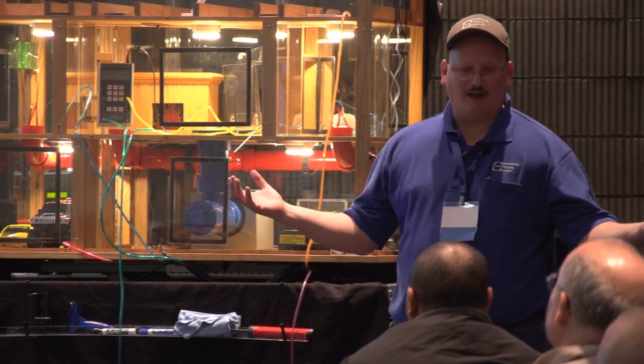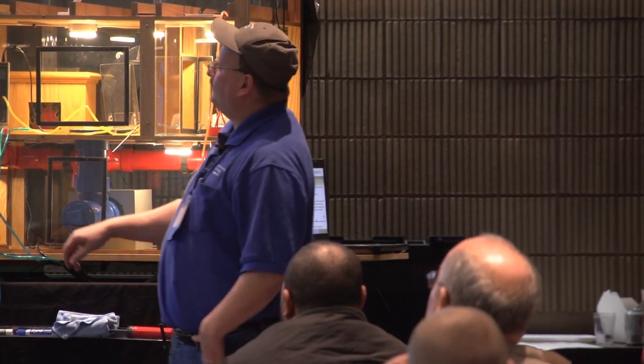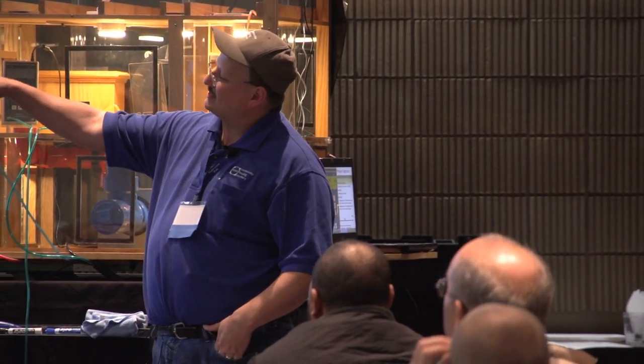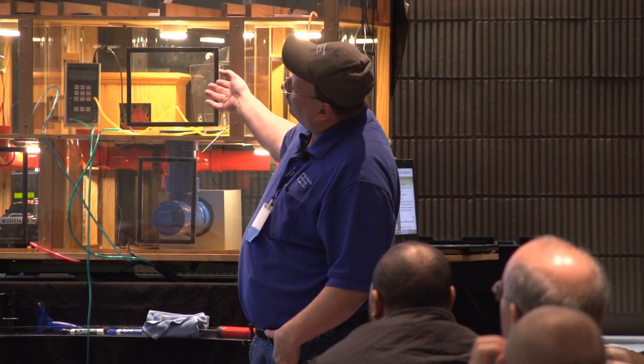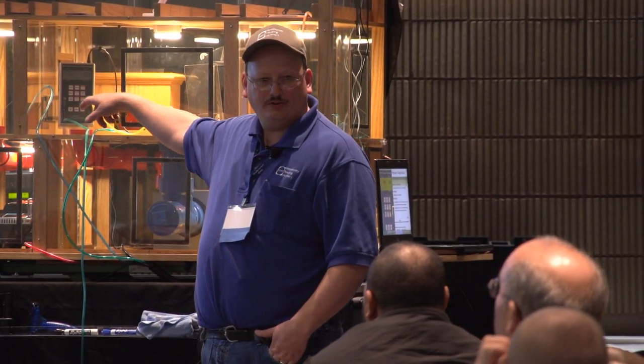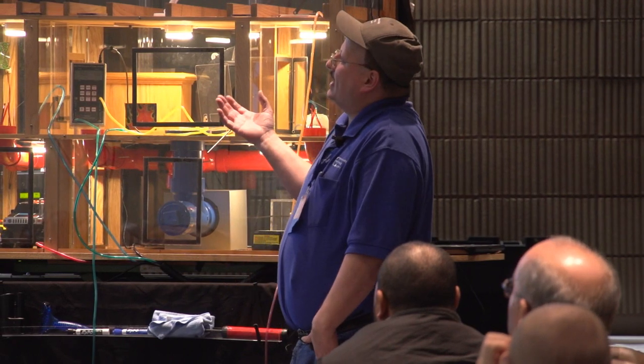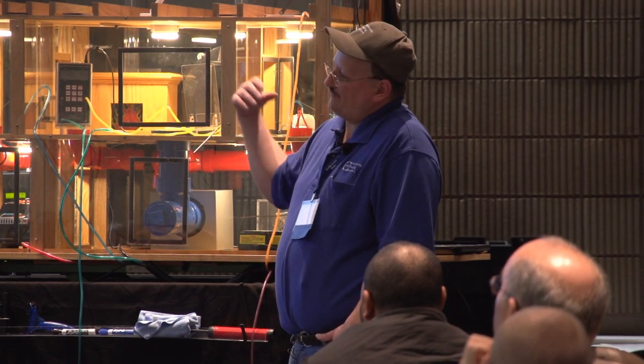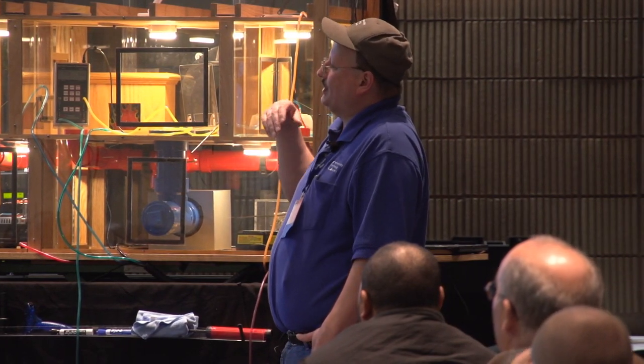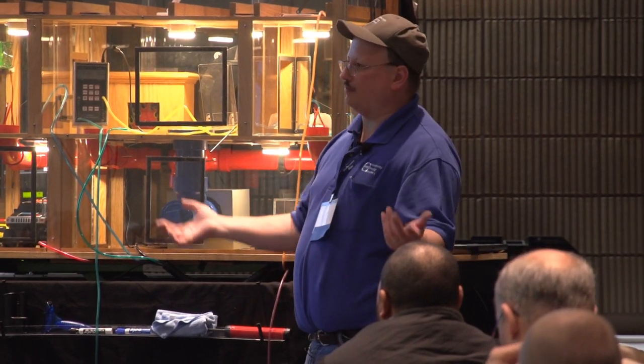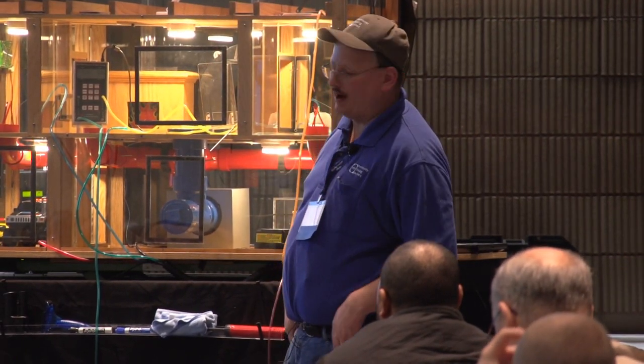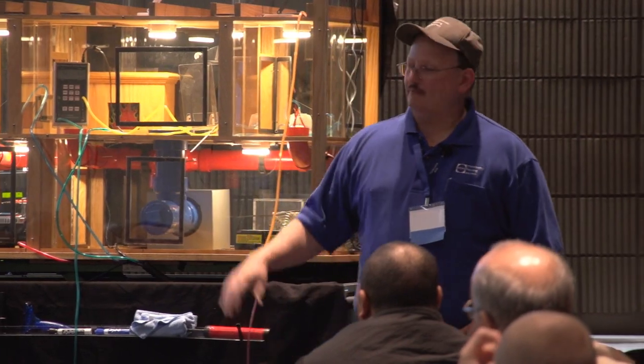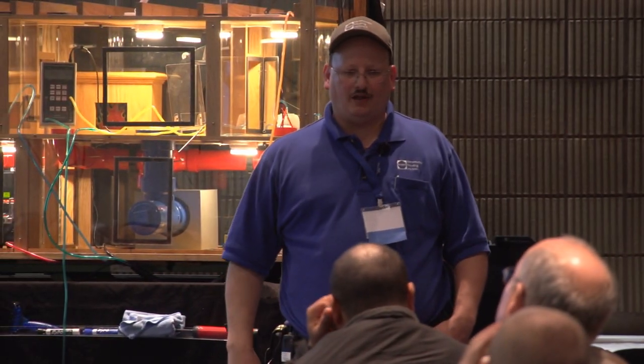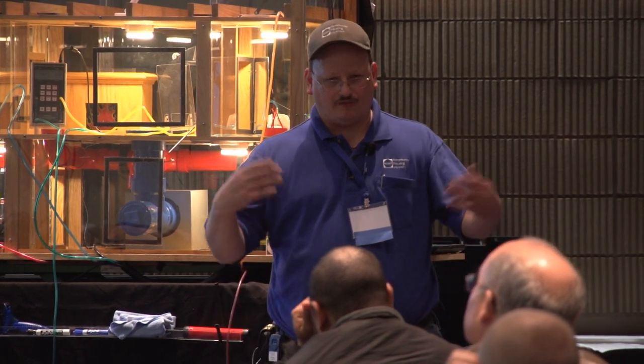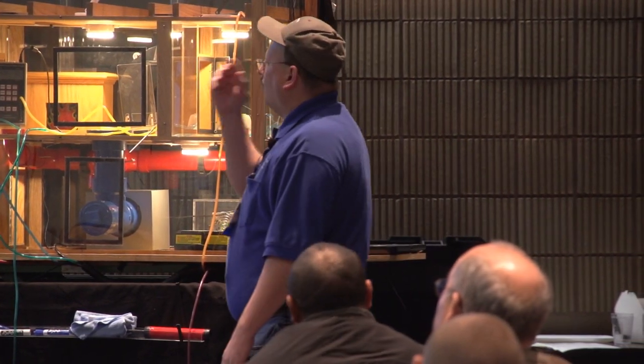They both read 50, right? Because now there is a little bit of difference. You notice the one on the A side says a negative and the one on the right shows a positive, but that's because I got my hose on the top versus the bottom. A lot of times I just leave my hose on the top, because I have my fan pressure hose on the top. I do my pressure pans on the top. That's just preference. I can move it to the bottom and it would say minus 50. But the 50 on that B side tells me what? Where's that space where the other end of that yellow hose is? Outside, right?